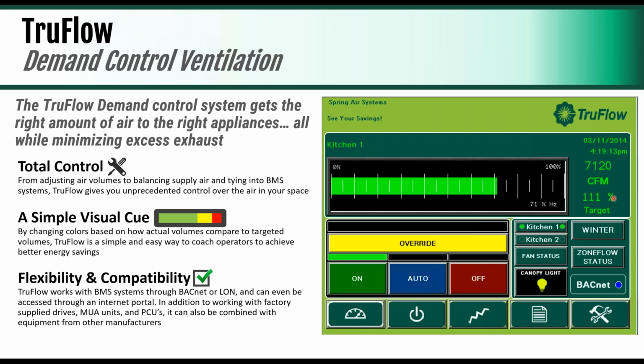And that is really through the use of the control panel here. So they're looking at a simple visual cue. The bar has 3 colors. It can be either green, yellow, or red. And anytime you're in the red, that's not necessarily a problem, but it means you're using between 90 and 100% of your exhaust capacity. That's great.